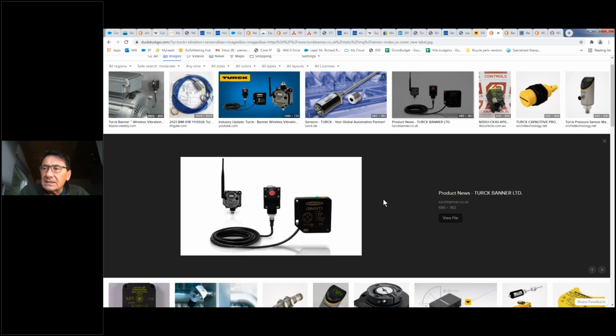It's as easy as this. You install the sensor. There's a software configuration mode for everything these days. And this software configuration mode allows you to run the sensor for a certain period of time, typically days or a week, under normal operation, and the sensor will set itself up with a profile of what normal operation is, and then prompt you in the software to set up warning and fault trip limits. At this point, you have your sensor set up as your watchdog, and now it is just a matter of getting that signal back to where you want it to get it to.